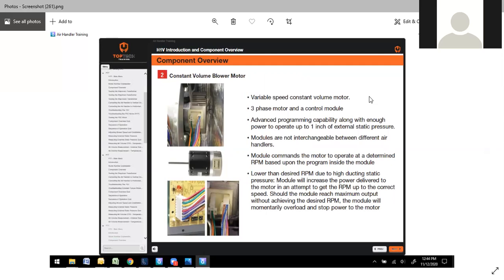So this particular motor here kind of gives you a good shot of the side of the motor, the board connections. It's a variable speed, constant volume, 3-phase motor with a control module. That's what the end bell right here is. Advanced programming capability, along with enough power to operate up to 1 inch of static pressure. Modules are not interchangeable between different air handlers. Module commands the motor to operate at a determined RPM based upon the program inside the module.